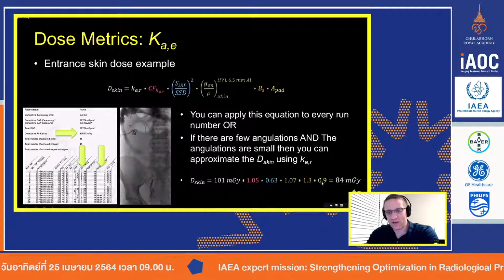So I have my max value, my total value, my cumulative air kerma. So what I'm going to do is I'm going to use that value times my correction factor that I had measured for my machine, times the correction for the distance, times the correction for the attenuation difference between air and soft tissue or skin, times the correction for the backscatter, times the fact that my pad and table reduced the dose by 10%. And so what the machine said on the monitor, what you saw as a physician, if you were the one that did this procedure, you would see 101 milligray at the end of the procedure. The reality is the skin had an entrance skin dose of 84 milligray.